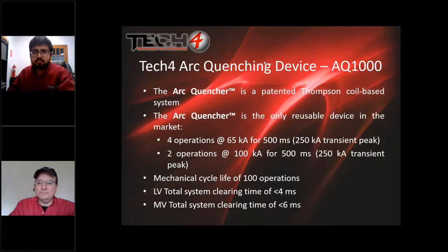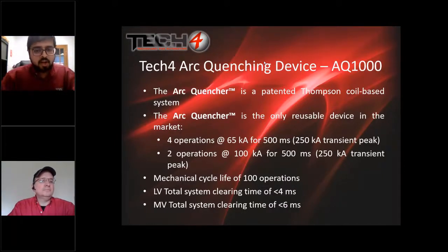So, a little bit about the Tech4 AQ1000 device. It's a patented Thomson coil-based system. It's the only reusable device in the market. There's a mechanical life of 100 operations, but it's limited to 4 operations on load, or for 65 kA, and 2 operations at 100 kA. There's also a medium voltage arc quencher. The clearing time of that is less than 6 milliseconds. But let's just concentrate on the LV AQ1000 device in this slide.